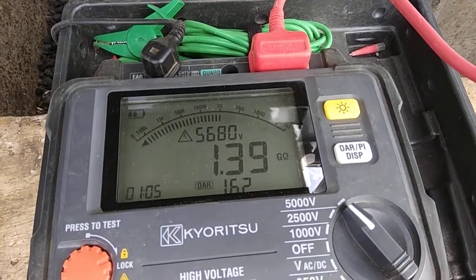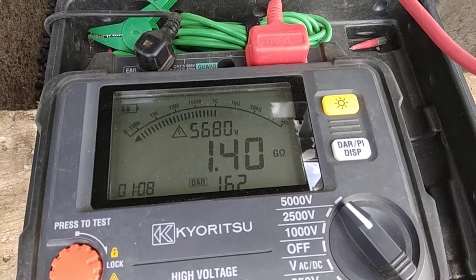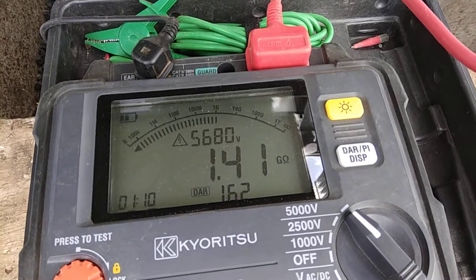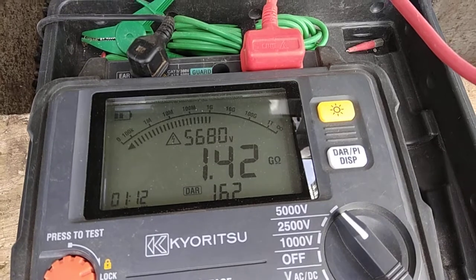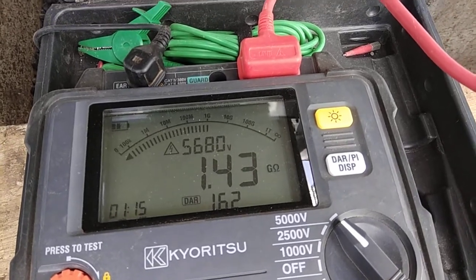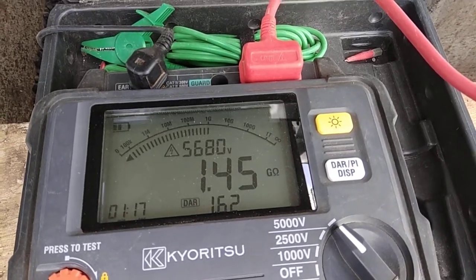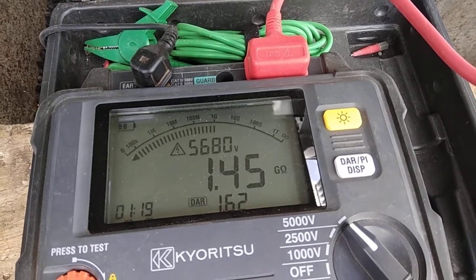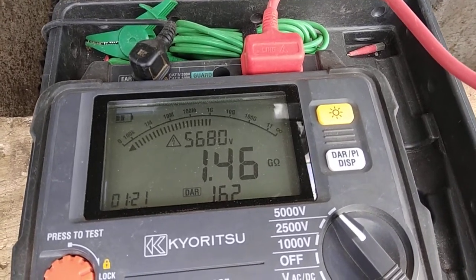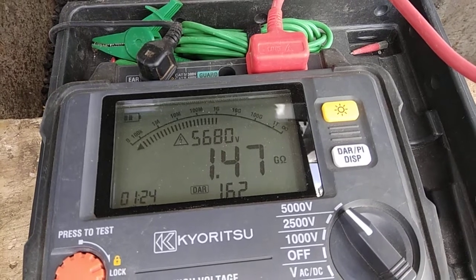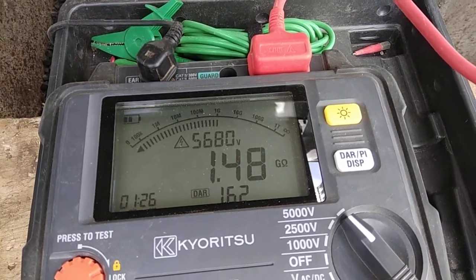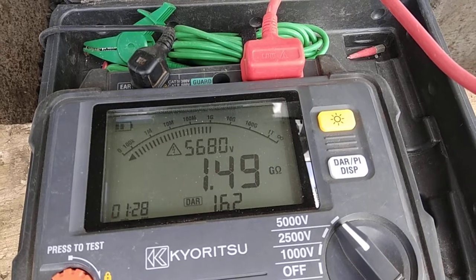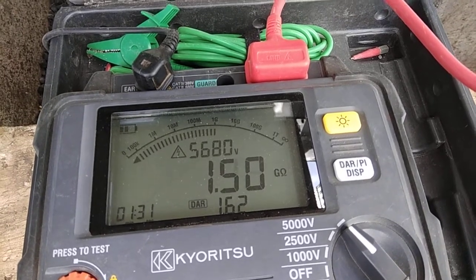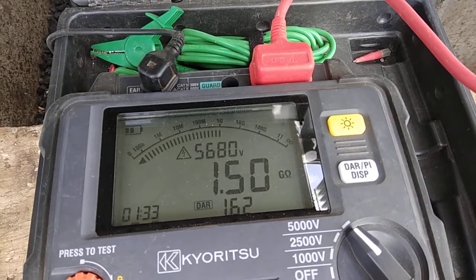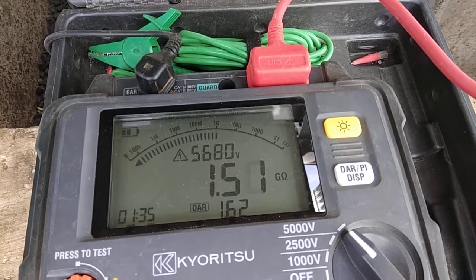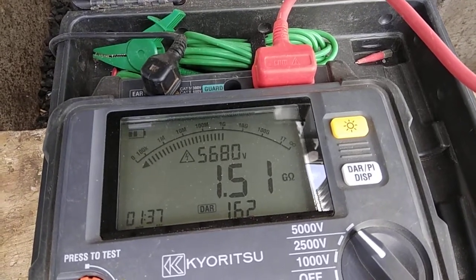So I have to tell you one thing. Every insulator has 4 currents associated with it. One is charging current, second is conductive current, third is the surface leakage current, and fourth and last one is the polarization current. Every insulator has a capacitive nature. So when we inject the voltage, the capacitor starts charging and then it becomes fully charged. There is no current. So the charging current flows from the start to 1 minute.